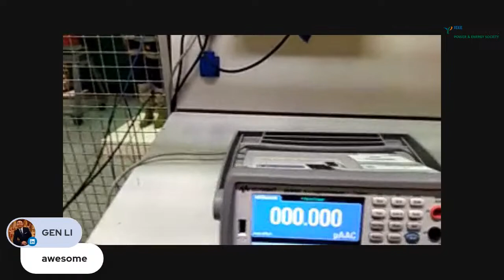So we put together a testing arrangement where we use a metallic plate that is energized. We will put 100 kilovolts on it. The clothing and the mannequin is in the high electric field, and we have cables that allow us to measure the current flowing through the suit and the current flowing through the mannequin as well.